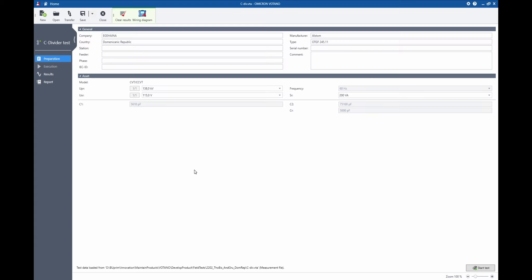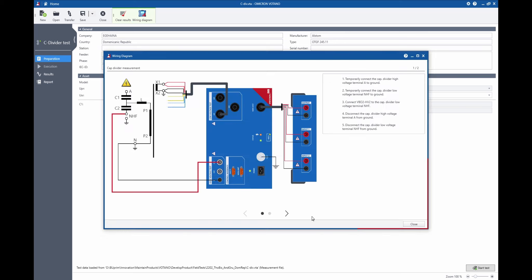To prepare the test I need to enter information like the rated ratio of the transformer and the nominal values for the capacitances. Then the first setup is like this where we connect to the secondary winding of the CVT and then to the lower part of the capacitor stack.